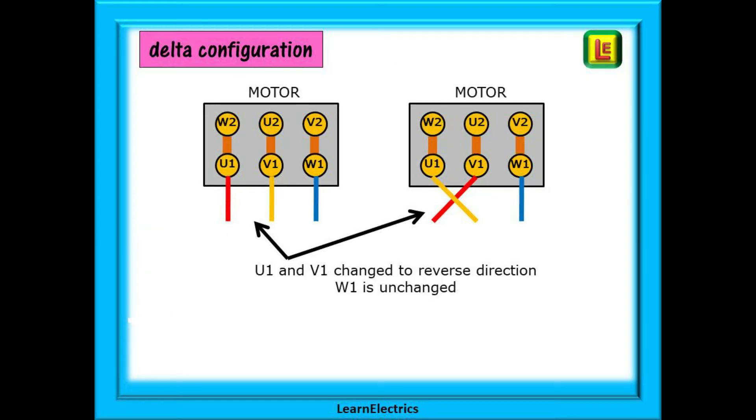If the motor is configured for Delta connections then we can do exactly the same. Leave the links as they are and swap any two incoming phases. This will change the direction of rotation. Just swap any two and leave the third as it is.